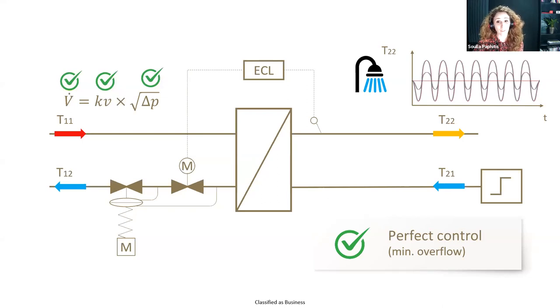As we install a motorized control valve, we gain the ability to control the KV, which is the valve opening part of the equation there. Since the system is dynamic and the differential pressure is changing all of the time, this will in most cases give you very poor control. And you can see that by the changing temperature in the graph at the top where the domestic hot water is coming from. With upgrading the substation with a differential pressure controller, we can achieve full authority over the flow control. And in most cases, we can achieve perfect control.